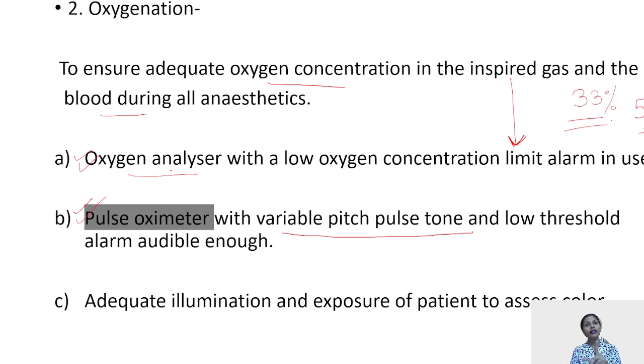So oxygen analyzers are used to check the oxygen concentration where? In the inspired gas. Second is the pulse oximeter, which tells you about the saturation of the arterial blood, that is the blood saturation inside the patient. So the second mandatory monitor to be present is the pulse oximeter, and this pulse oximeter has a variability in the pitch of the pulse tone, which changes with the changing saturation, so that even if the anesthesia provider is not looking at the monitor, the pitch of the pulse tone would tell how the saturation is going on. And lastly, obviously, you should have adequate light in order to assess cyanosis.